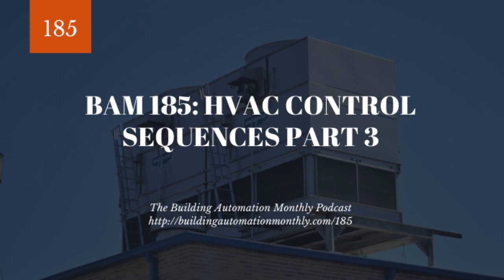So our primary thing with air handling units is moving the air volume, because that is how we are going to change temperature and humidity. Remember, our primary variable in all airside control is airflow. A lot of folks will say it's temperature. A lot of folks will say it's humidity. Some folks will even say it's CO2, but none of that matters if we aren't flowing air. I mean, you can control temperature to the nth degree, but if you can't get the air into the space, none of that matters.